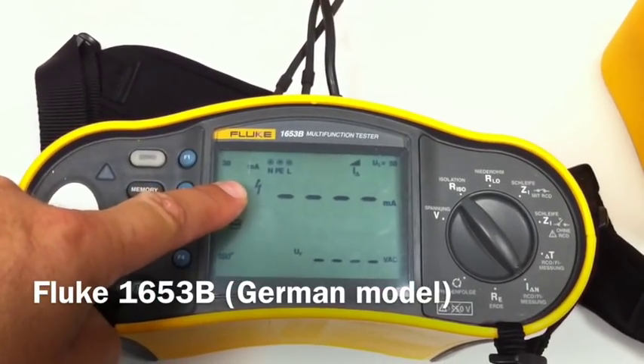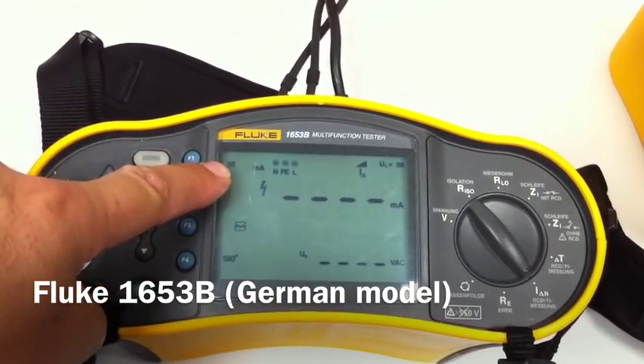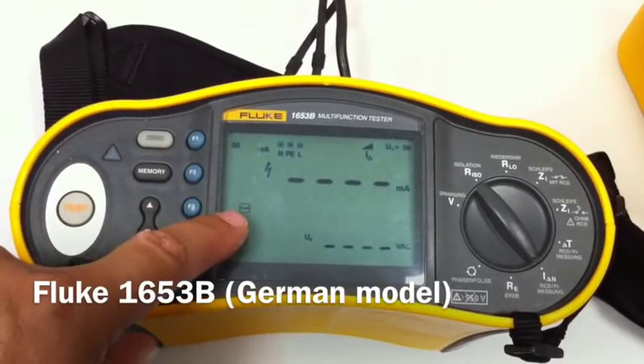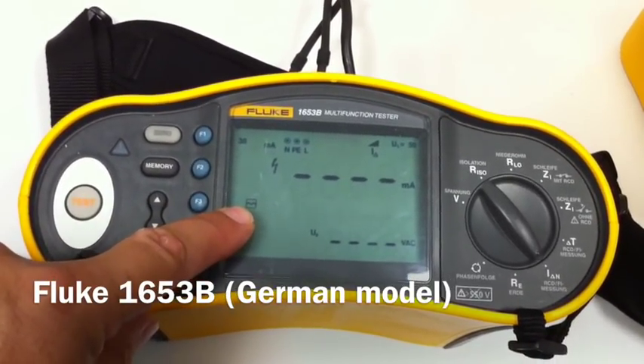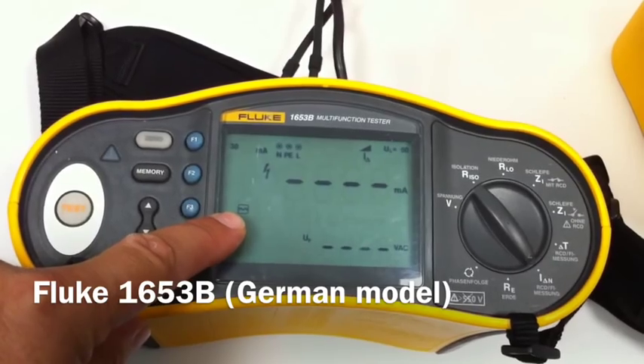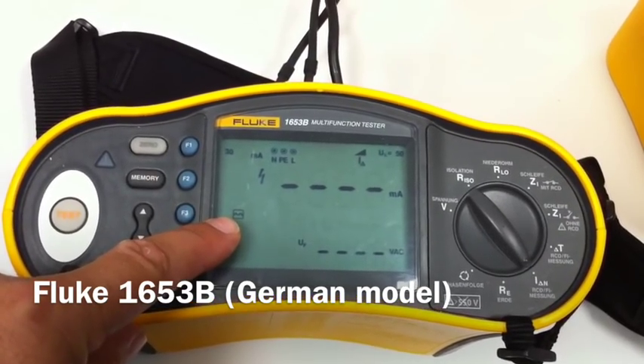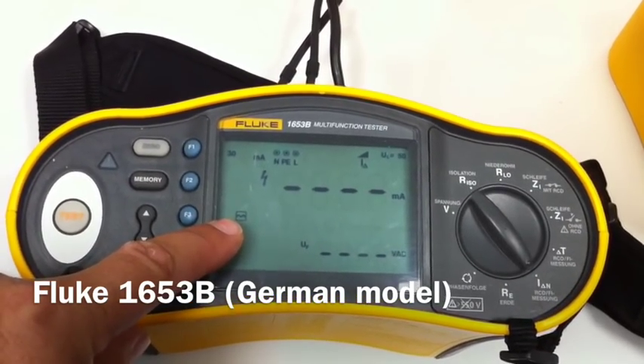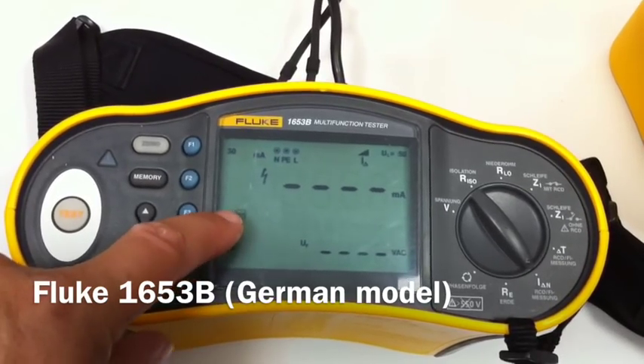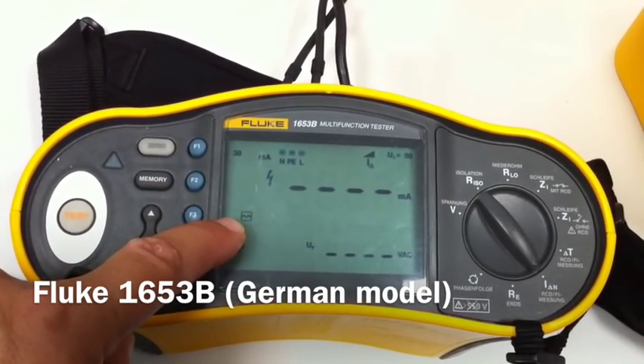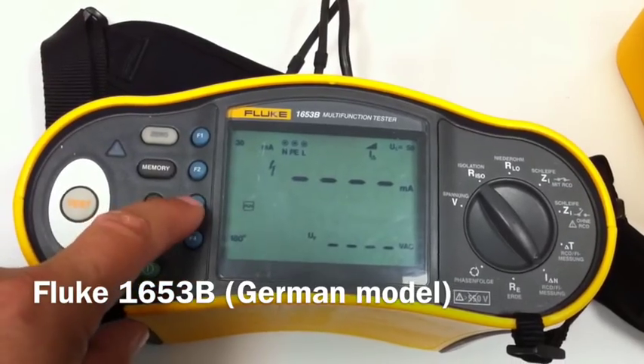The voltage is on. We have a 30 milliamp trip, and here's the symbol for the A type, which is with the pulsing current detection as well. That's slightly different from what the manual shows, but this is the right one.